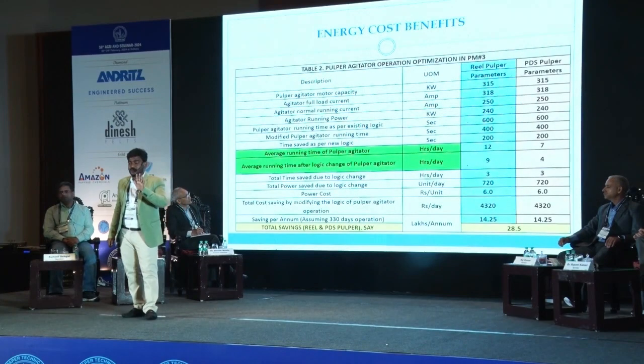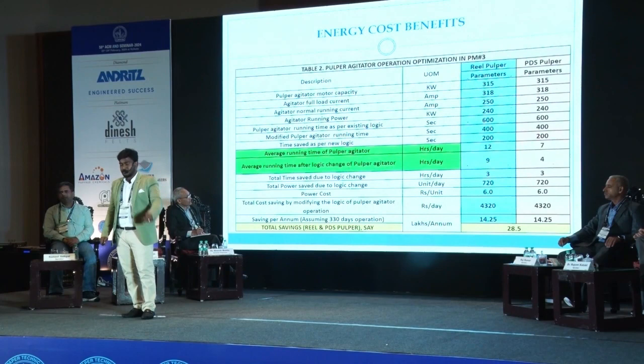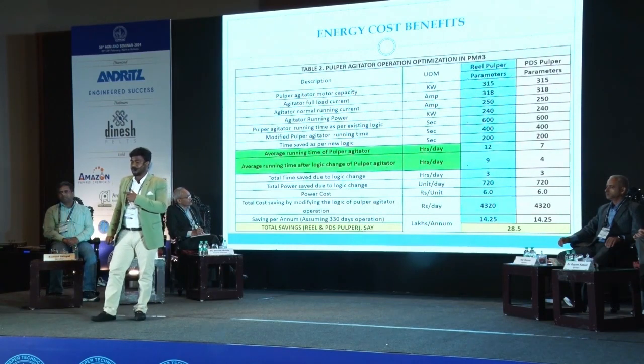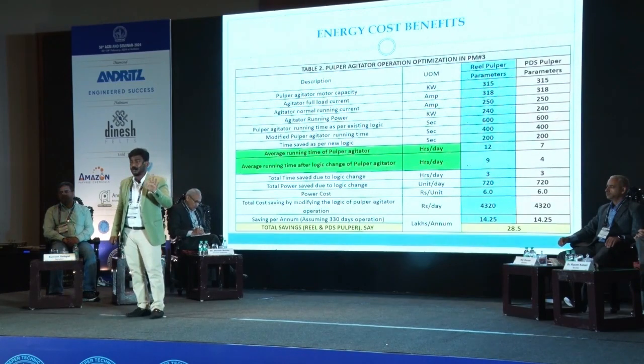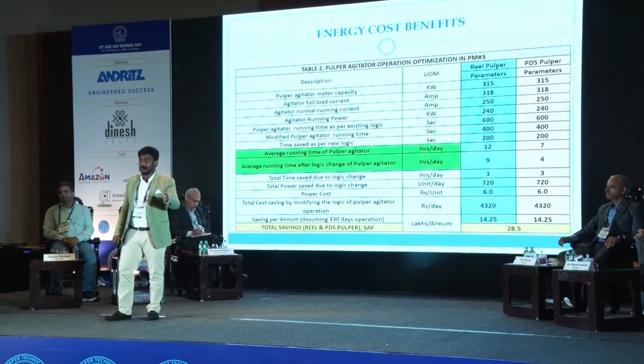When you look at the cost saved from this minor modification, as I said, this motor capacity is 315 kilowatt and running power is 240 kilowatt. So you saved 3 hours of running power. So 3 into 240, 720 units saved per day. Considering 6 rupees per unit, we are saving 4,320 rupees per day for each pulper.